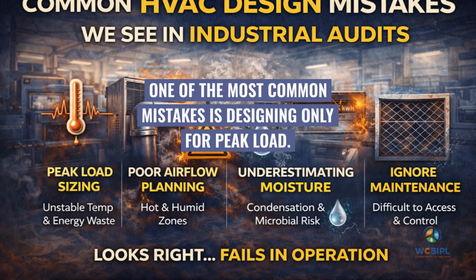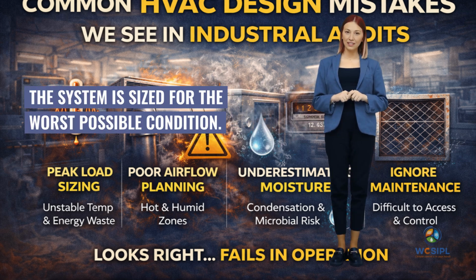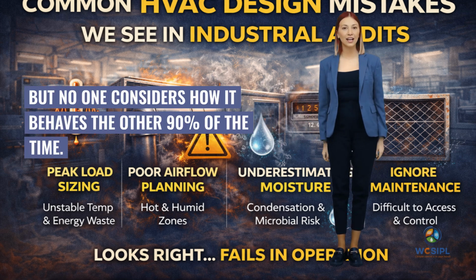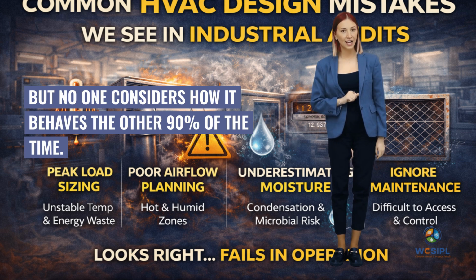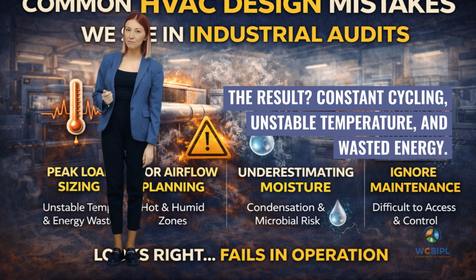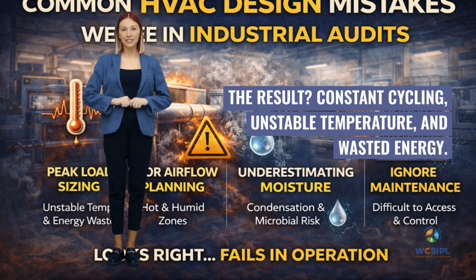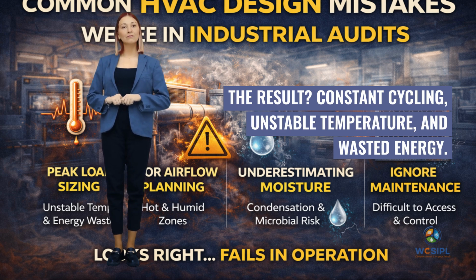One of the most common mistakes is designing only for peak load. The system is sized for the worst possible condition, but no one considers how it behaves the other 90% of the time. The result: constant cycling, unstable temperature, and wasted energy.